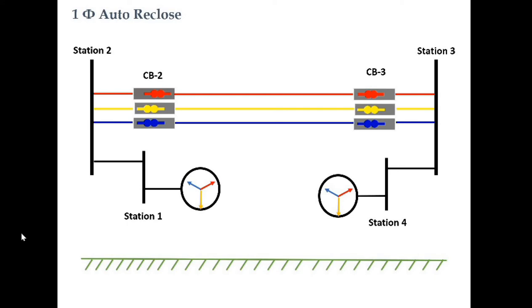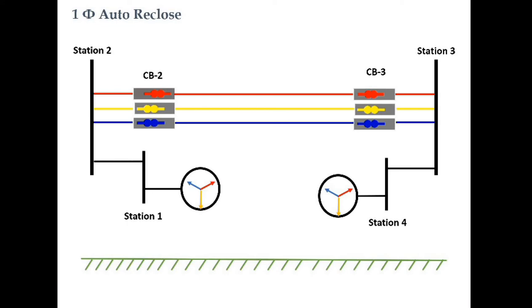In transmission lines, 70 to 80 percent of faults are of transient nature. To reduce the outage time due to such transient faults, auto reclosure schemes are used in transmission lines. However, when a fault persists in the line, after auto reclosure, if the relay senses a fault, it gives a trip command to the circuit breaker once again and the line trips. In such cases, we say auto reclosure is unsuccessful.